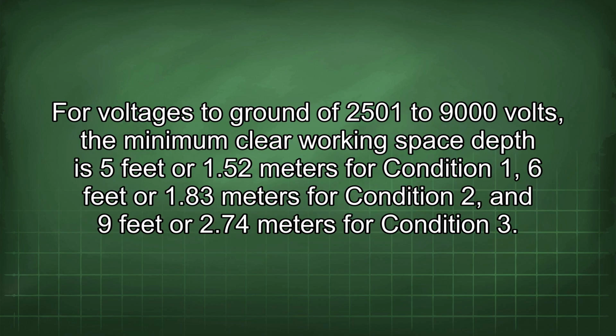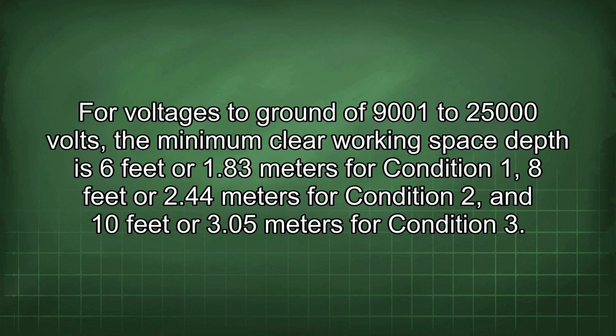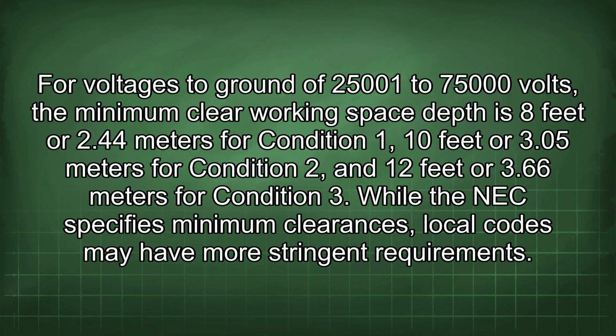For voltages to ground of 2501 to 9000 volts, the minimum clear working space depth is 5 feet or 1.52 meters for condition 1, 6 feet or 1.83 meters for condition 2, and 9 feet or 2.74 meters for condition 3. For voltages to ground of 9001 to 25,000 volts, the minimum clear working space depth is 6 feet or 1.83 meters for condition 1, 8 feet or 2.44 meters for condition 2, and 10 feet or 3.05 meters for condition 3. For voltages to ground of 25,001 to 75,000 volts, the minimum clear working space depth is 8 feet or 2.44 meters for condition 1, 10 feet or 3.05 meters for condition 2, and 12 feet or 3.66 meters for condition 3. While the NEC specifies minimum clearances, local codes may have more stringent requirements.